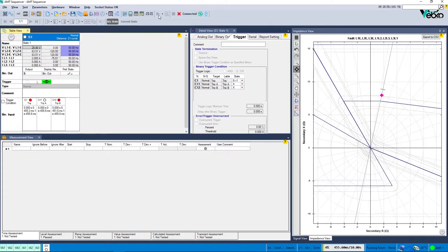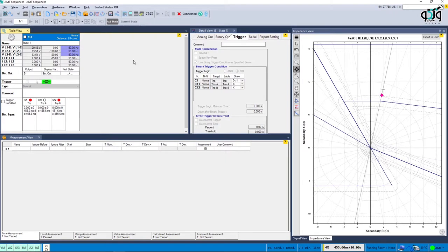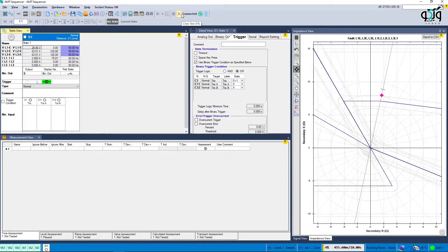As you can see, from trips in zone 1 and zone 2, in addition to the physically wired contact C1, the trip is also recorded through contacts C11 and C12. You can also send a change of status command to the relay by enabling or disabling binary output.